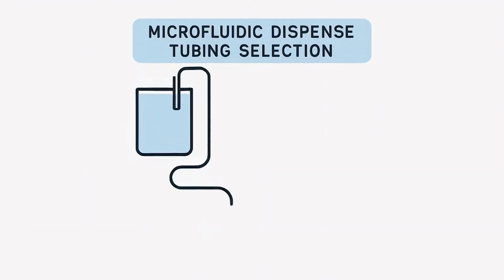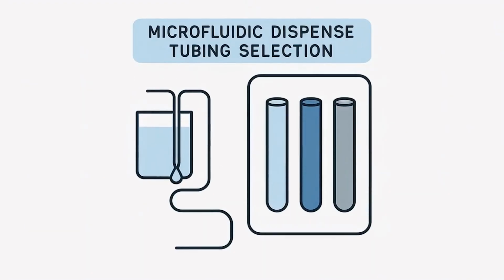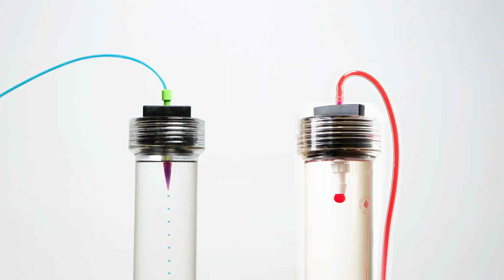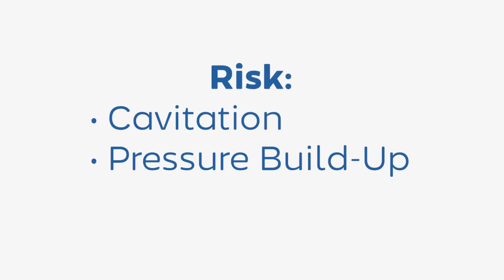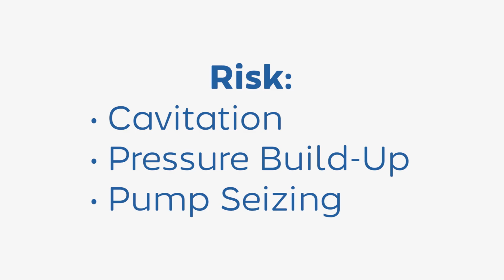Tubing selection should be matched to both dispense volume and application requirements. For dispensing applications below 10 microliters, a small diameter tubing is recommended to maintain fluidic precision and for easier priming. Tubing durometer, its softness or hardness, also influences flow stability. Softer tubing can dampen pulsation, while stiffer tubing may provide better precision and accuracy. Incorrect tubing selection can lead to cavitation, pressure buildup, or pump seizure. When selecting tubing, it is important to consider your application's needs to get the best outcome from your pump.